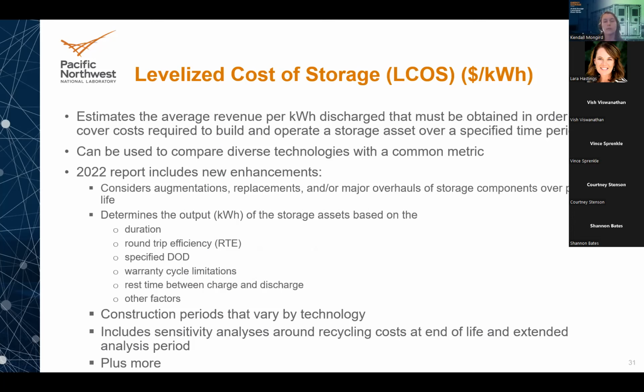The 2022 report includes some new enhancements for this metric, including augmentations, replacements, and major overhauls, where we've now set a minimum life of 20 years for battery energy storage - so between 20 and 25 years for their project life. However, your cycle life or calendar life will place limitations where you have to replace or augment that storage block to maintain operation for that time period. So we've now incorporated all of these different replacement or augmentation schedules into this LCOS calculation.